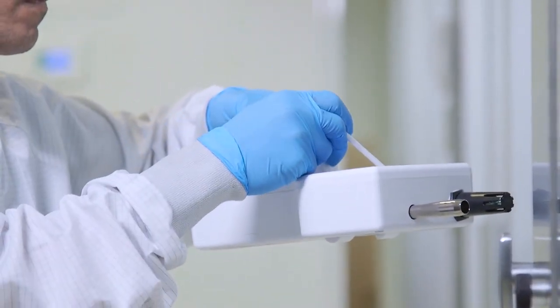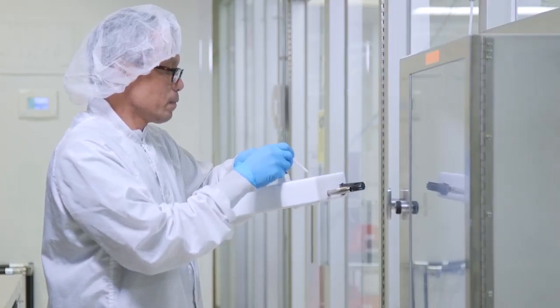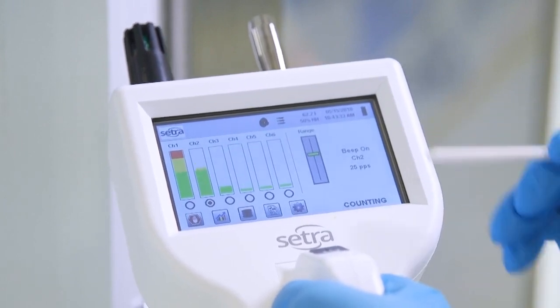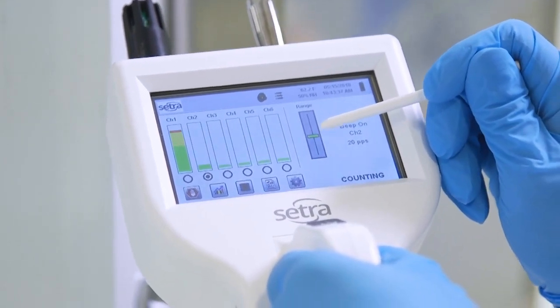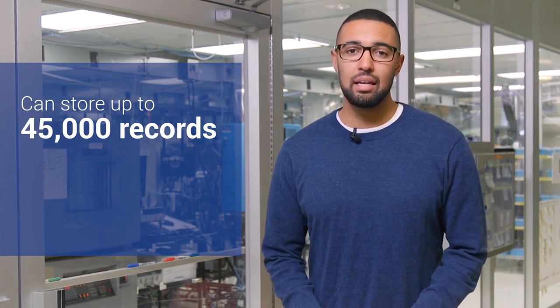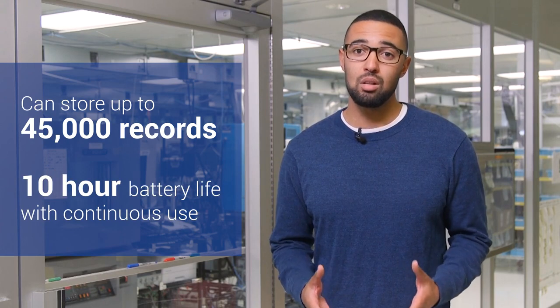Particle counters like Setra's 8000 series make it easy for you to be in charge of your environment. An intuitive icon-based interface lets you know exactly what's going on, and flexible connectivity options let you easily collect and store data. Added memory and extended battery life makes these devices even more user-friendly. Each Setra particle counter can store up to 45,000 records and can continuously operate for 10 hours on battery power alone.